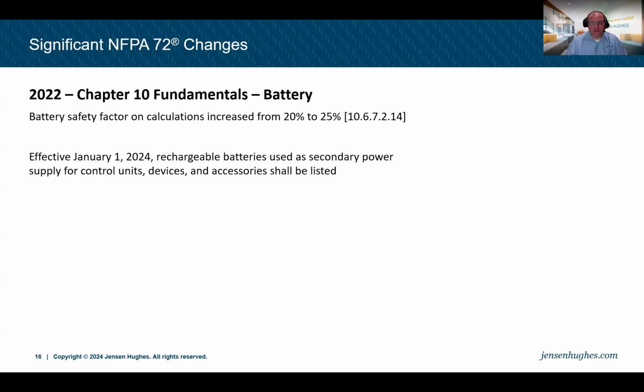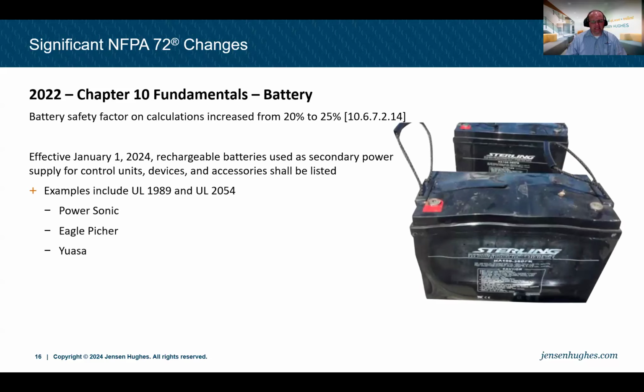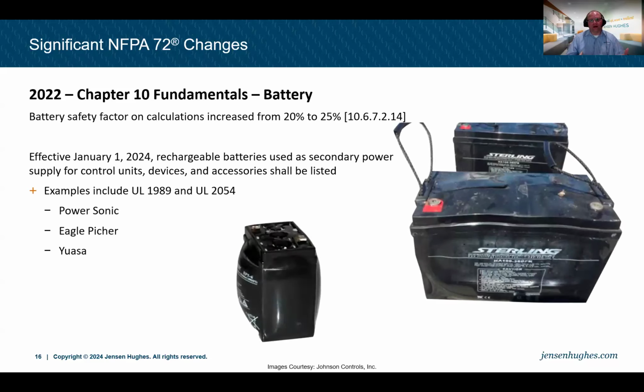Also, effective January 1st, 2024, any battery we use as a secondary power supply for a control unit, notification appliance power supply, and those kinds of things, must be listed. In this case, listed to something like UL 1989 or 2054, some kind of commercial listing that guarantees the quality of the battery. And there are many manufacturers producing good batteries out there. We want to use those good quality batteries and not use off-market or refurbished batteries. That's not the kind of battery we want to be using in our fire alarm systems.